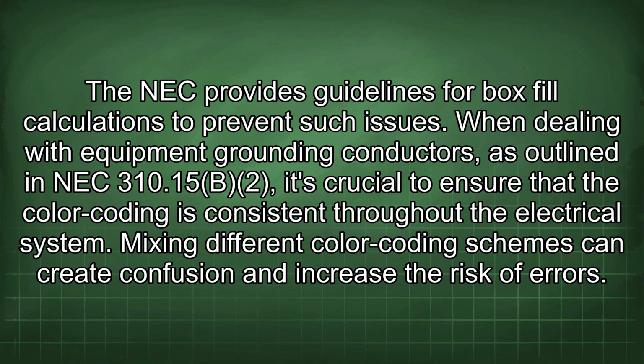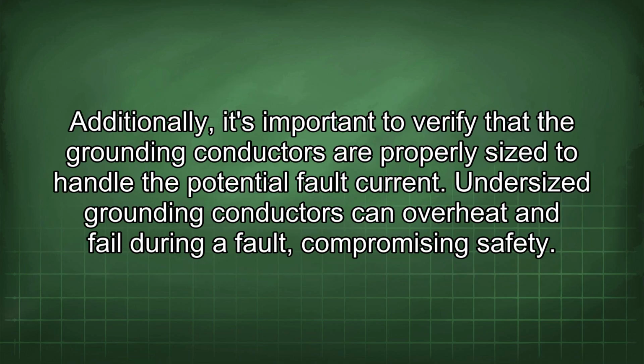When dealing with equipment grounding conductors, as outlined in NEC 310.15b2, it's crucial to ensure that the color coding is consistent throughout the electrical system. Mixing different color coding schemes can create confusion and increase the risk of errors. Additionally, it's important to verify that the grounding conductors are properly sized to handle the potential fault current. Undersized grounding conductors can overheat and fail during a fault, compromising safety.